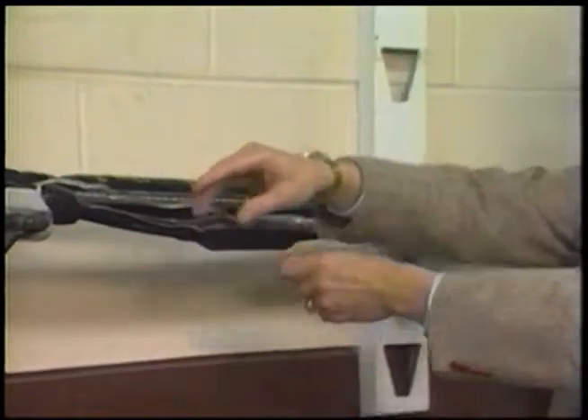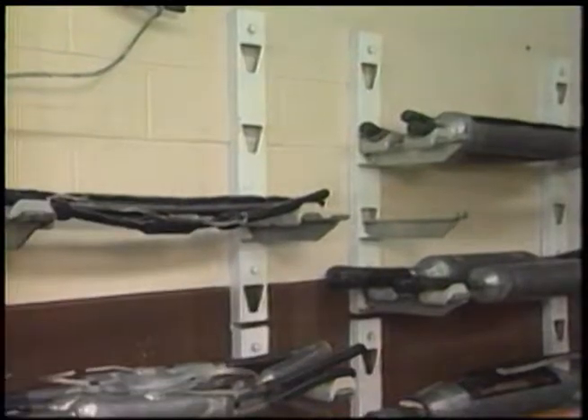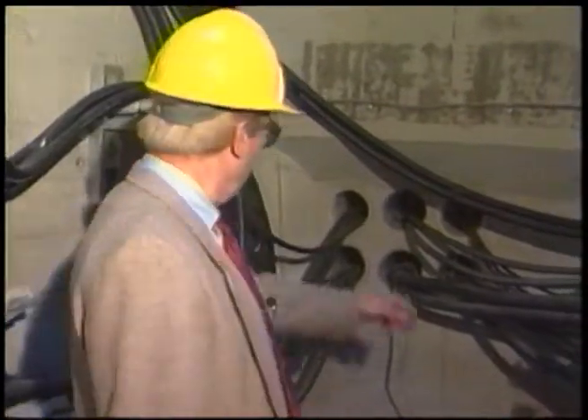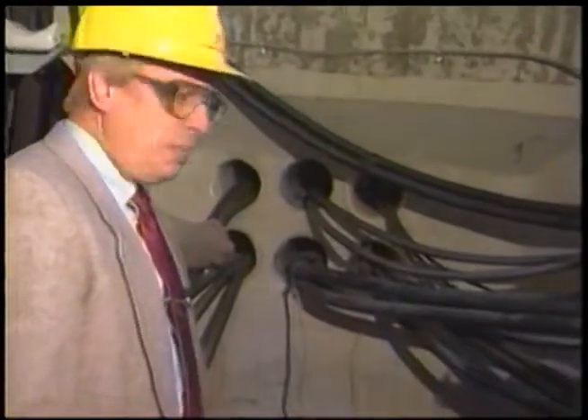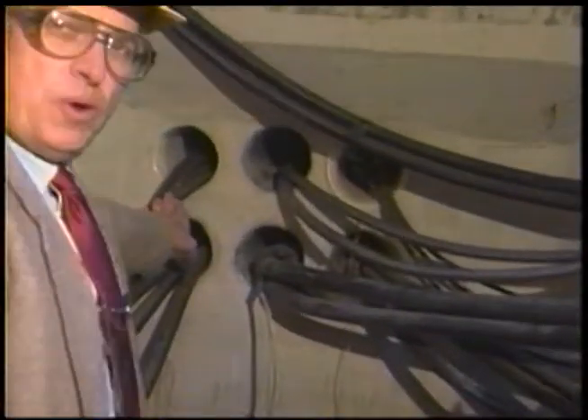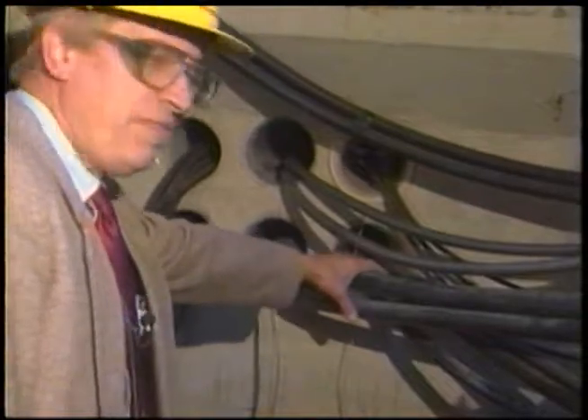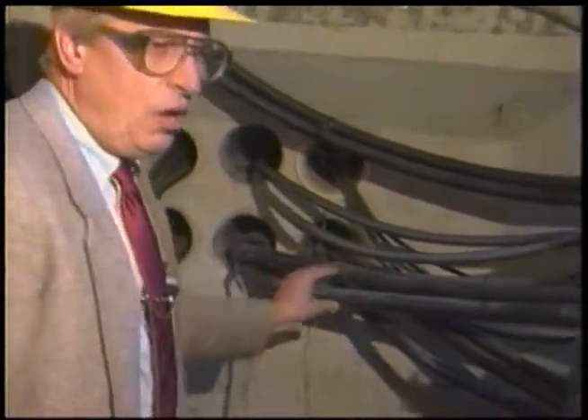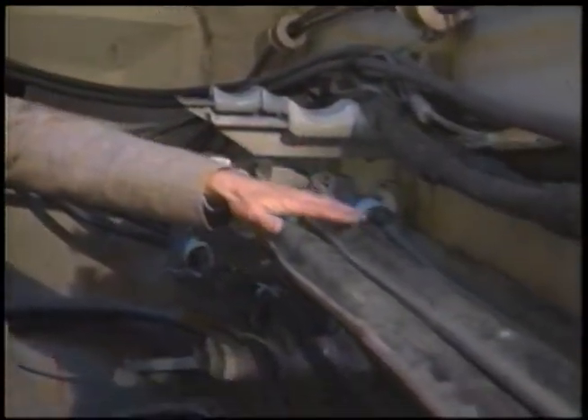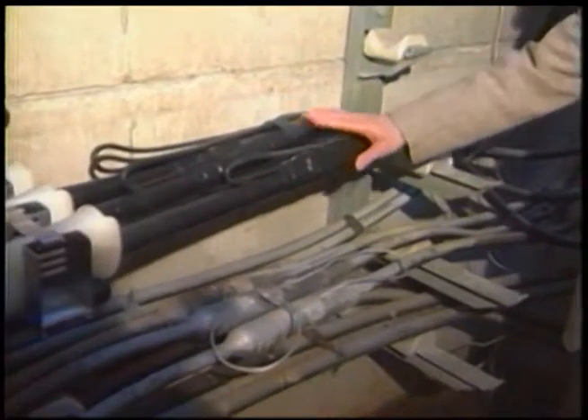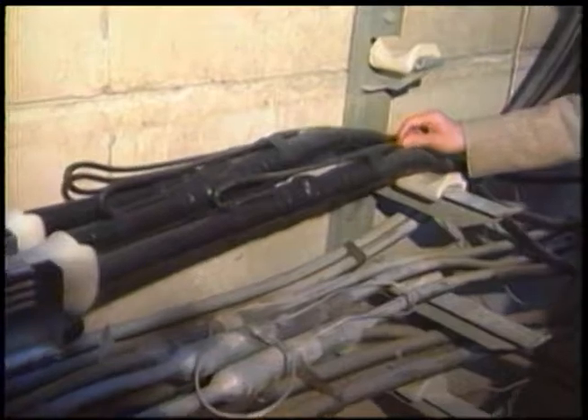Let's go into a manhole and look at the grounding inside the manhole. As you can see, we are in a typical manhole. Behind me are some ducts with cables coming out. Up on top is a 120 volt cable, down below is 15,000 volt cable. On each side are racks of cable. This is a cable that has a joint in it with the ground coming out.